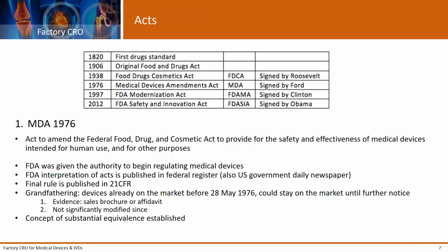Important to understand is that devices before May 28, 1976 could stay on the market until further notice, and that the concept of substantial equivalence was established. And this is very important to understand since we will be talking about 510K. Okay, please go ahead.